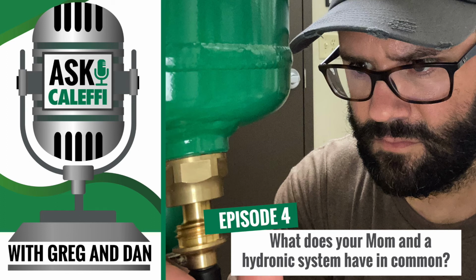So if you find you're going out to a system and you're replacing these variable speed drives and you're consistently having to do that, and you don't have magnetic separation, most likely you have a lot of magnetite in the system that's getting drawn into the magnets of that pump, causing premature failures. Right. It'll lock it tight. Yeah, absolutely. I think almost any variable speed pump manufacturer out there will recommend that you have the magnetic separation to protect the pumps. Right.